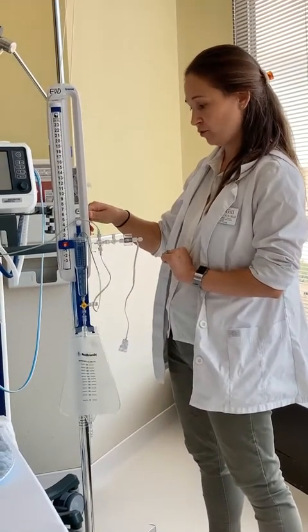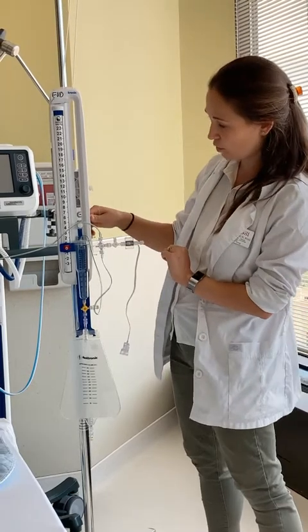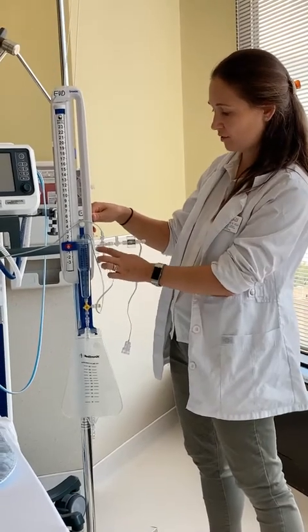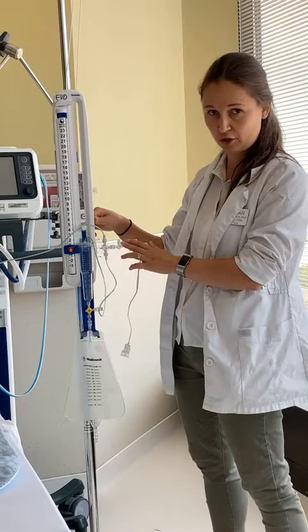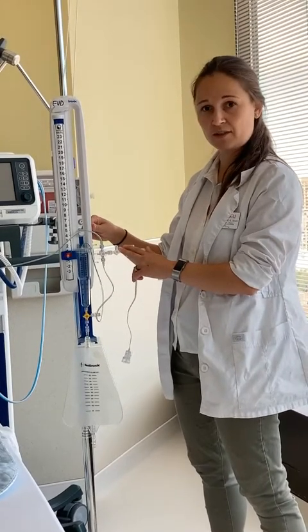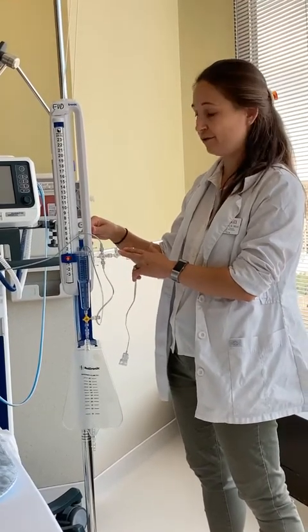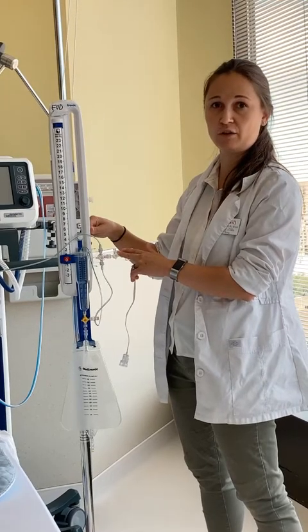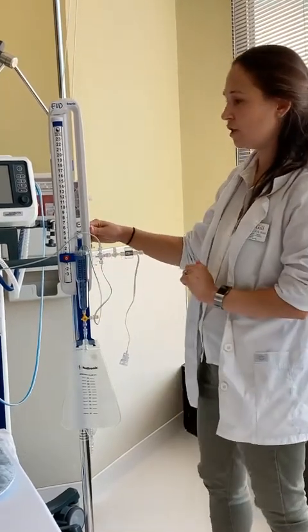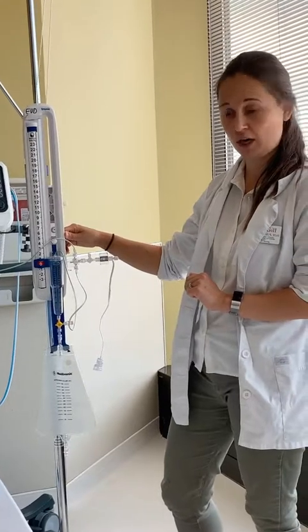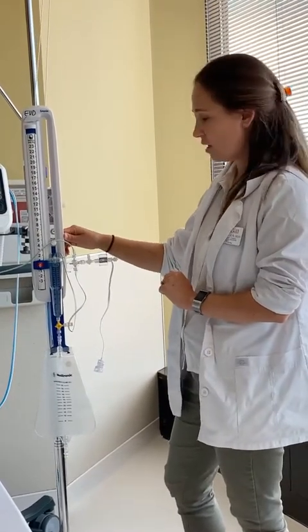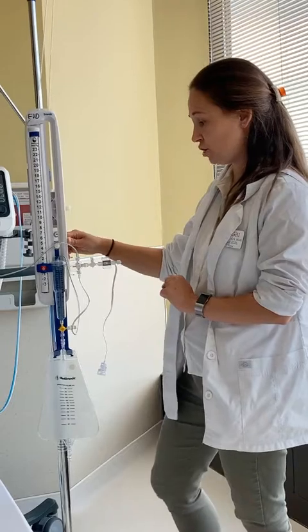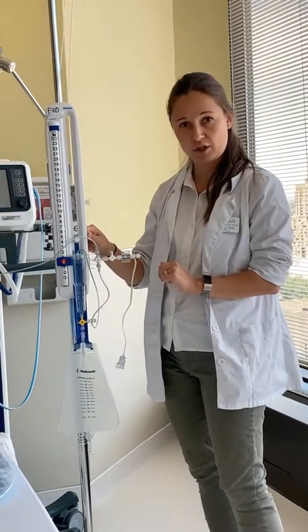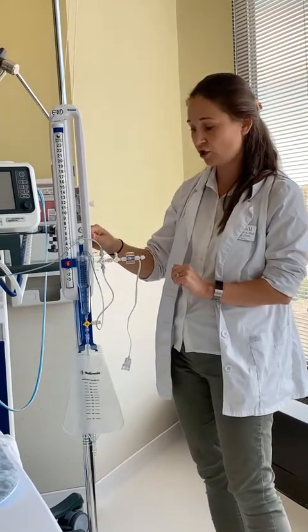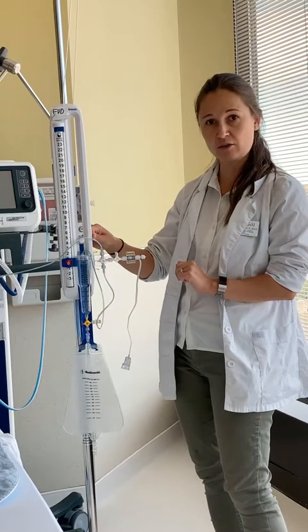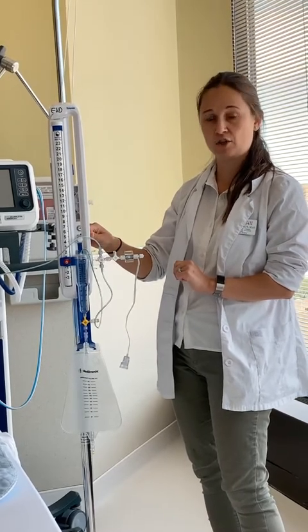Now, another thing to note is that if your system is open to CSF drainage as well as to measure intracranial pressure, the intracranial pressure is going to be affected by the pressure of the fluid draining into this chamber. So your ICP reading is actually not going to be correct. If you need to measure your intracranial pressure while your patient is on continuous CSF drainage, you need to temporarily stop the drainage and then measure your ICP.